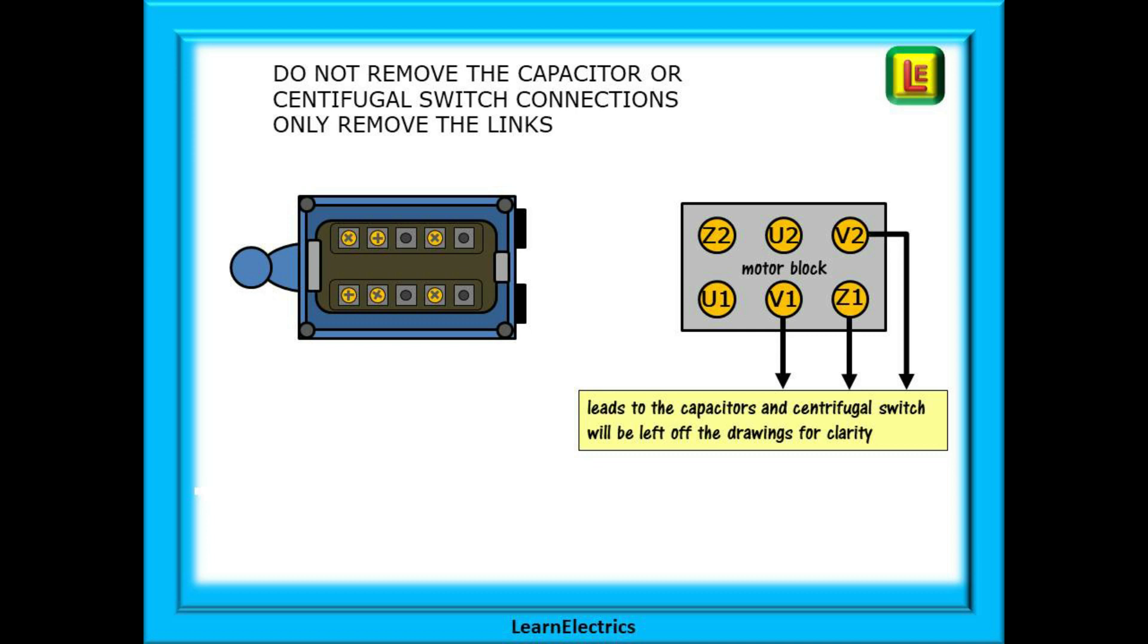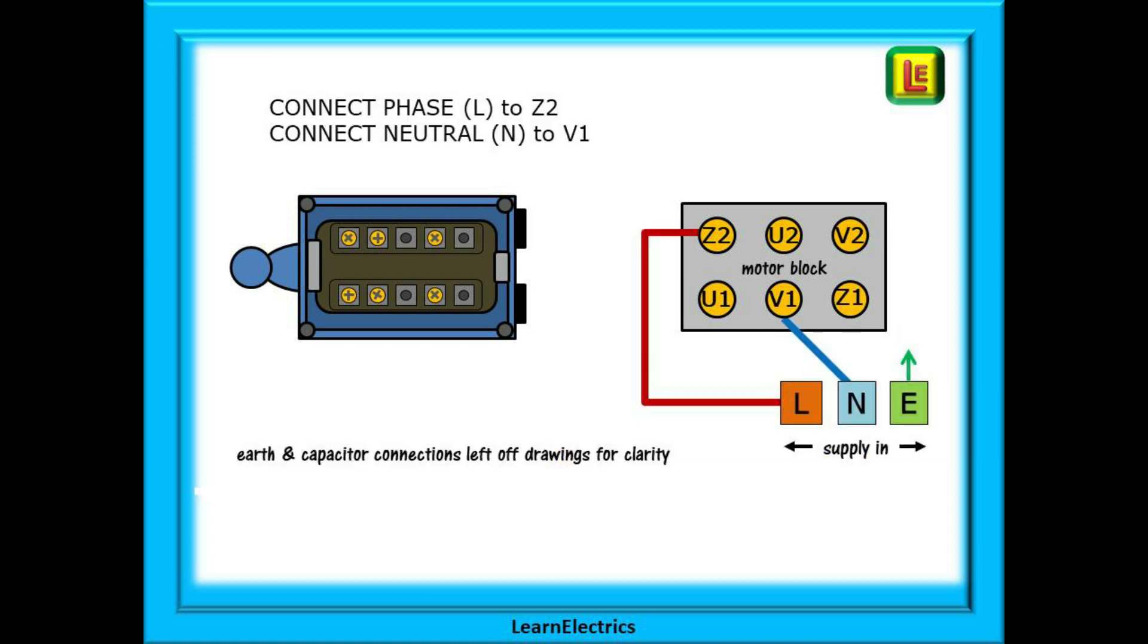So now we can start connecting the new switch to the motor block. As already mentioned do not remove the wiring to the capacitors or centrifugal switch. Only the links should be removed. After removing the links you should reconnect the incoming phase to the Z2 terminal and the neutral to the V1 terminal.